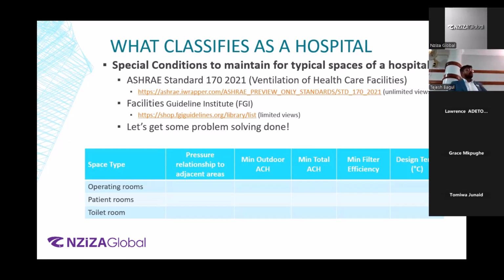You will also need to find the minimum outdoor ACH. As I mentioned in the earlier session, ACH means air changes per hour. In some part of the world, it is also called ACPH, but the definition stays the same. Then we need to also check from that table itself the minimum total air changes per hour. One more thing that we need to find out is the minimum filter efficiency. And last but not the least, the design temperature in degrees centigrade.